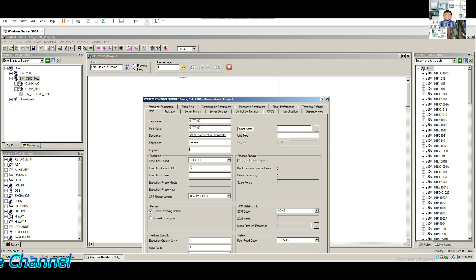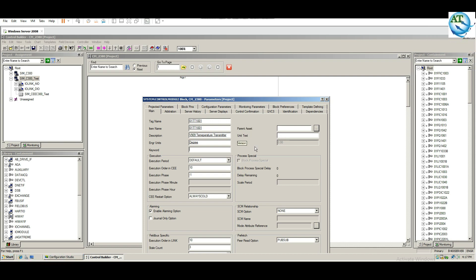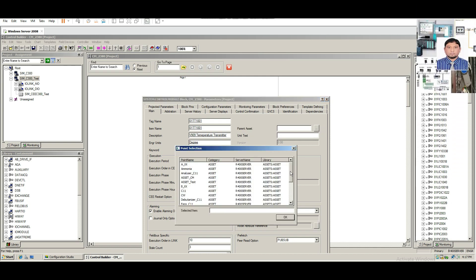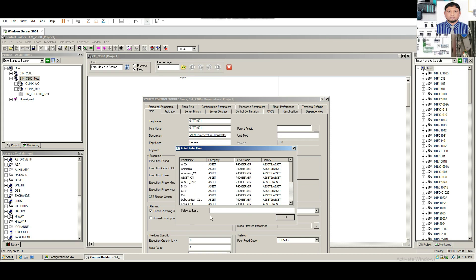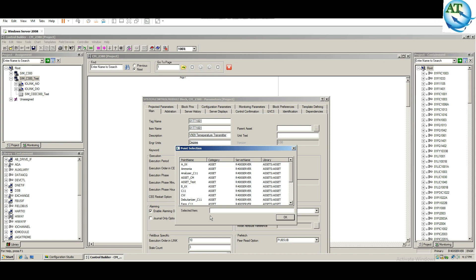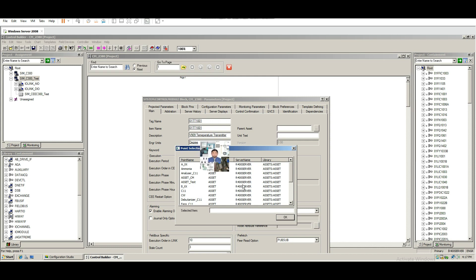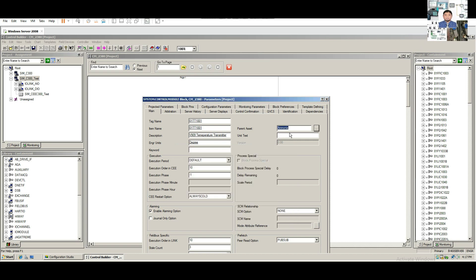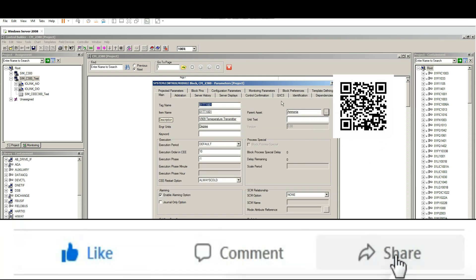Here the most important parameter setting is the Parent Asset. If you don't select this parent asset, you cannot load this program to the server. Click the three-dotted button and all the parent assets that you have already configured will appear. In my previous video I showed how to make a parent asset in Honeywell DCS system. Here many parent assets are available — select any one. We select 'Ammonia' and press OK. Parent asset selection is completed. All other parameters shown in the same block can be left in default mode, then press OK.